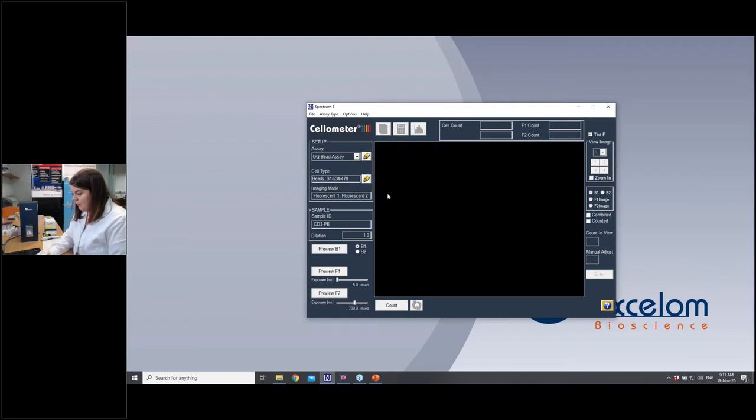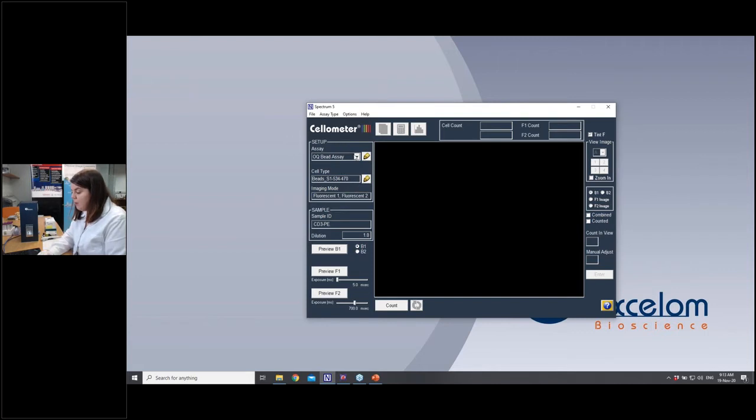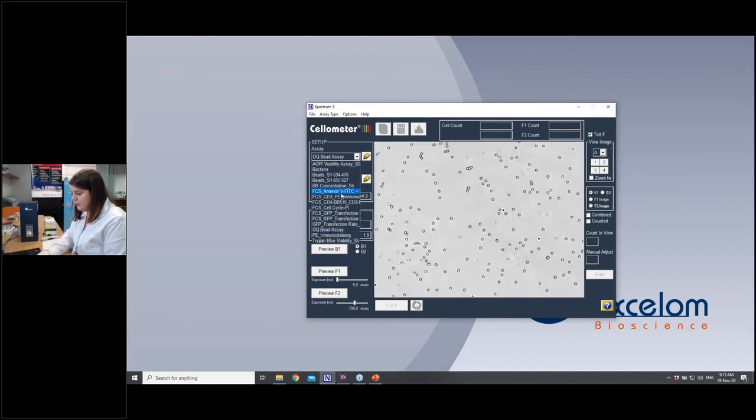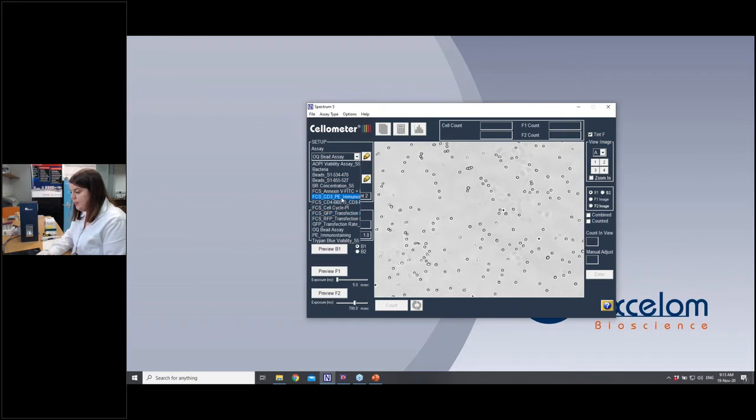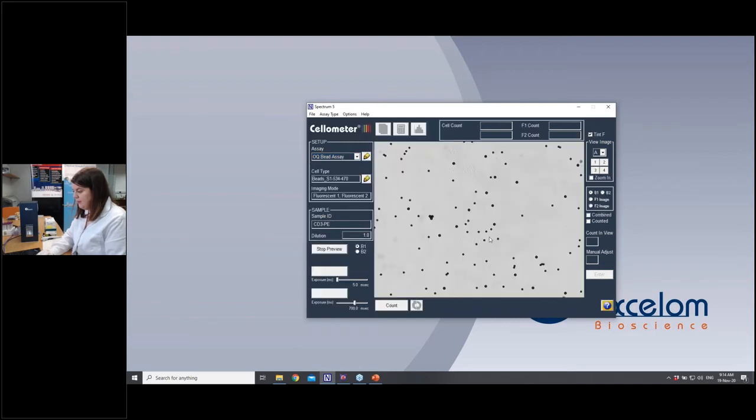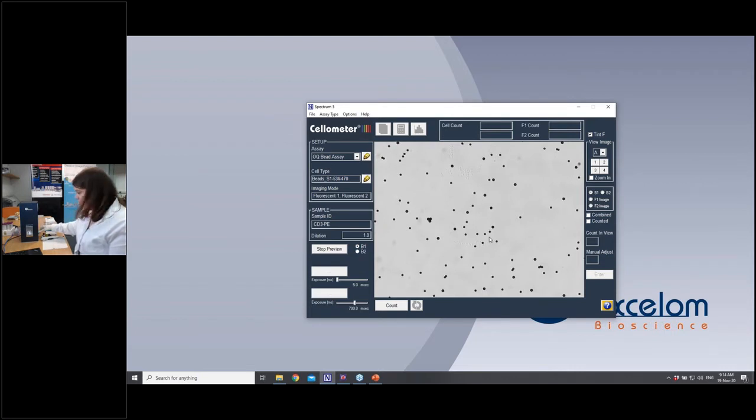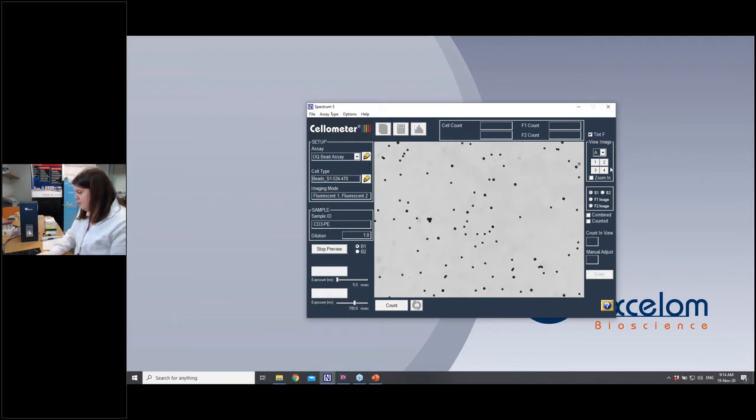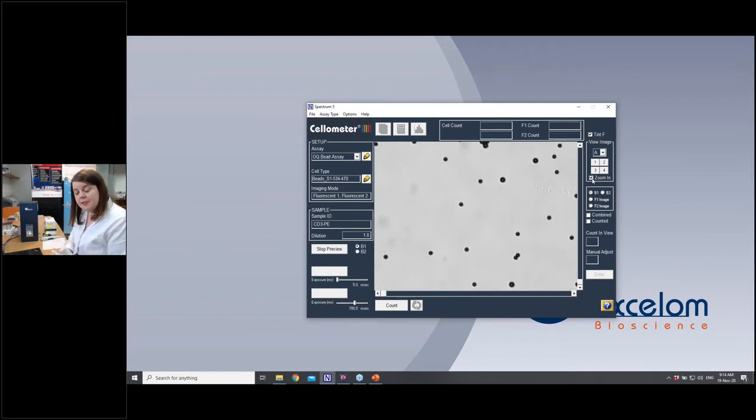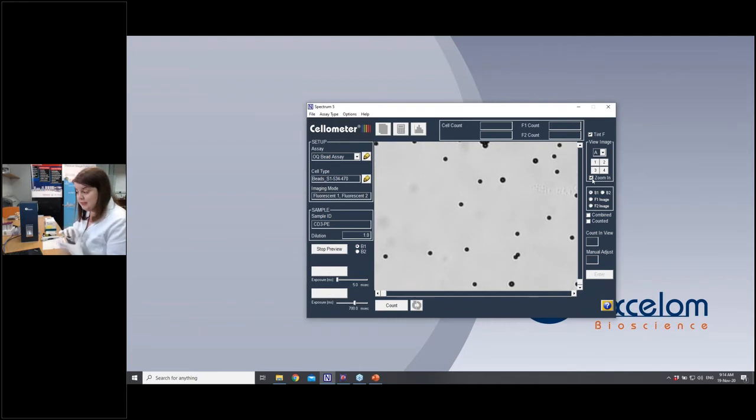So I'll go to the software now, which is on a laptop that's connected. What we have in the software is we have a number of plug and play assays that will already be loaded for you. So I've got an AOPI assay here that's already loaded, but we also have a choice of lots of different assays as well here. So we've got cell cycle, transfection efficiencies, immunostaining, apoptosis, and we've got viability up there. And I'll show you some examples of all of those as well. But for now, we're using the bead assay and I'm going to preview my brightfield image. So these are the beads. These are live. You'll hopefully see them move about if I wiggle the slide. So this is a live image here. We have a focus dial on the edge, which you can turn to perfect that focus. I'm going to zoom in a little bit just so we can see those a little bit better. Now, the beads don't look quite like cells. They don't have that crisp, dark edge and bright center because they are spherical beads, but we can still see that these are nicely in focus.